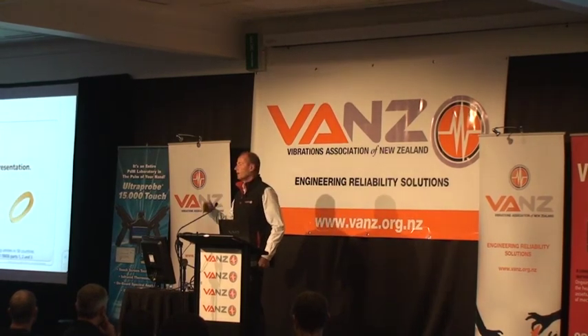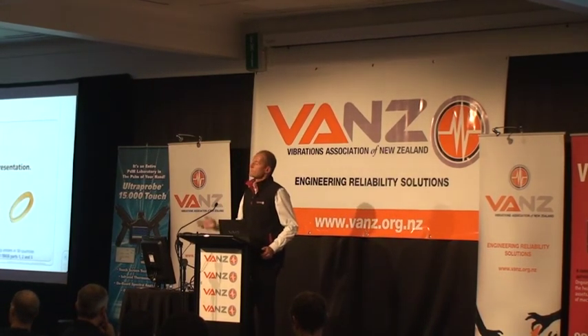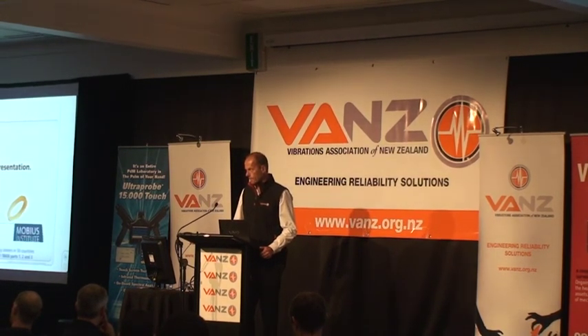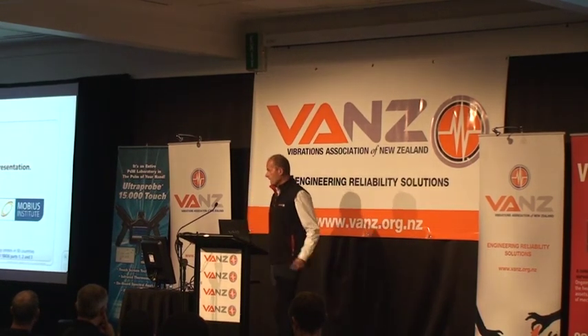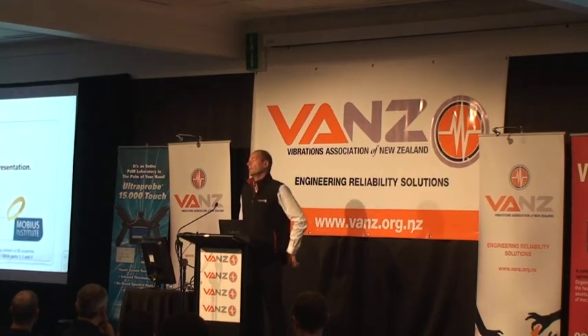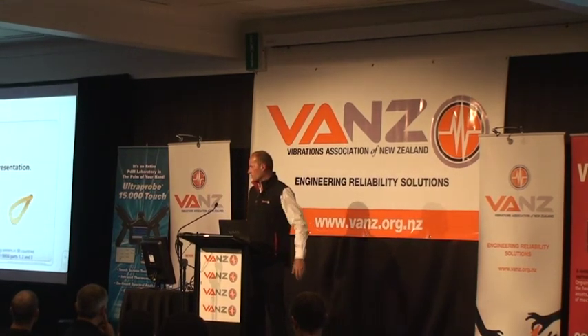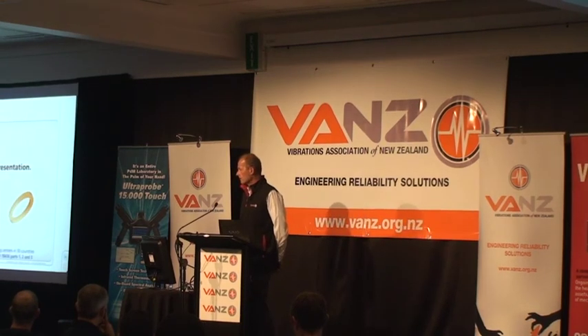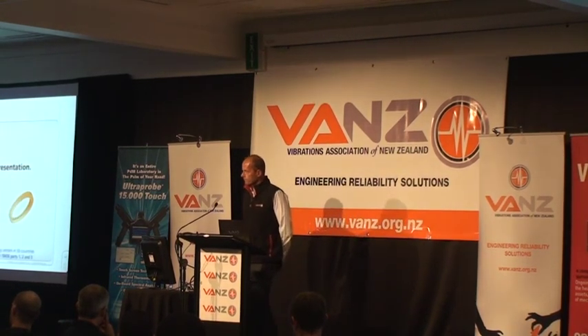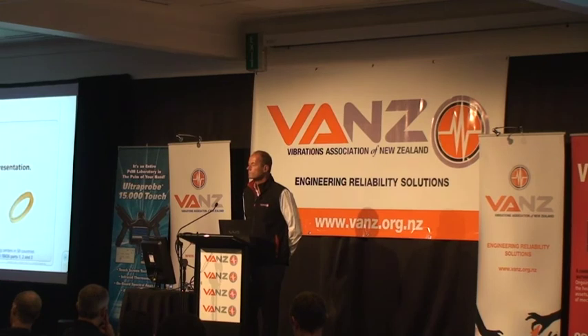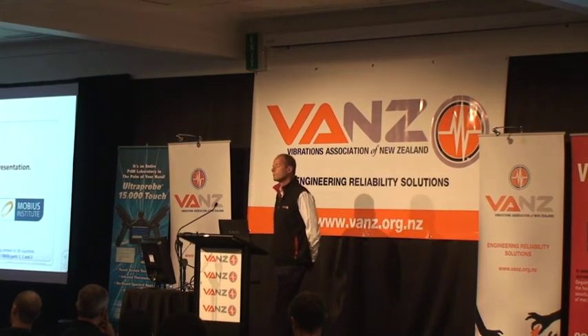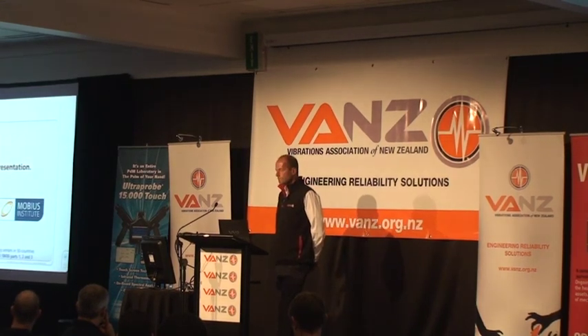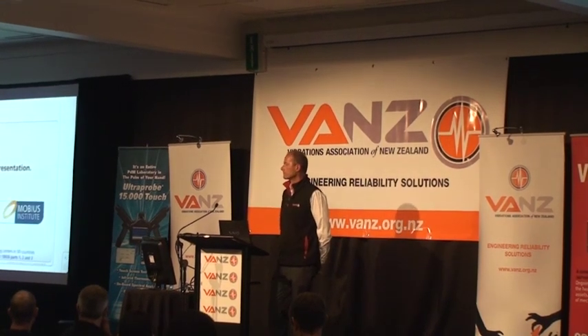Right. So sometimes it's useful to use laser triangulation in addition to that, just to see if it's really a material inhomogeneity effect or if it's a surface effect, about the glitch removal. There are different probes now that are being used to look at that displacement, but proximity probes are the most common out there for these sorts of things. It's just about knowing your sensor, and none of these sensors is ever perfect, so they always have some side effects, and sometimes if you're running into strange effects, take it into consideration. Yep, good point. All right.